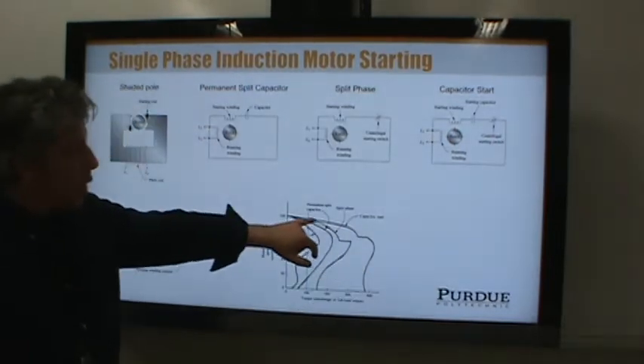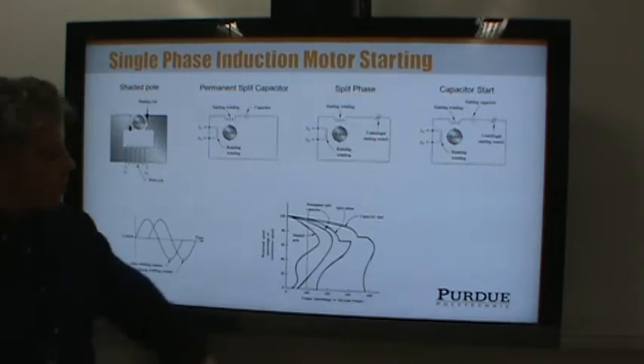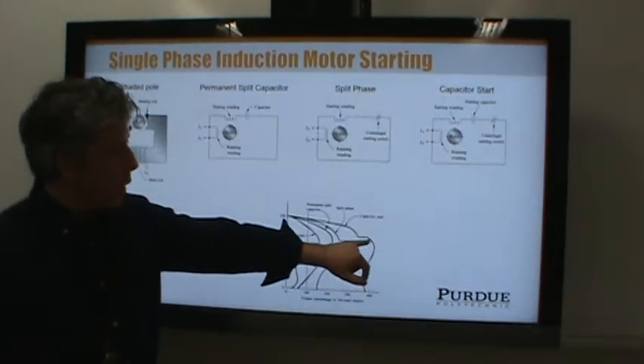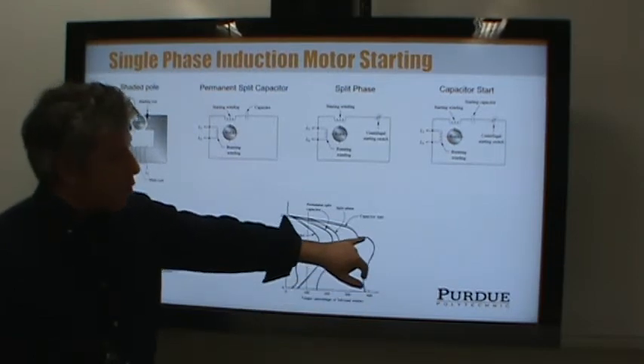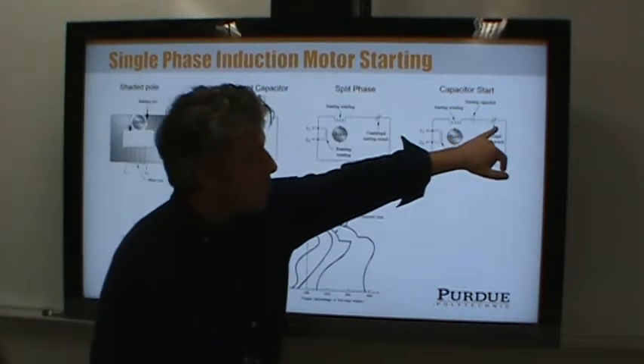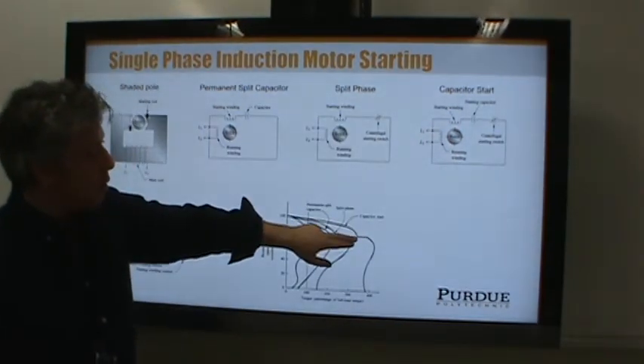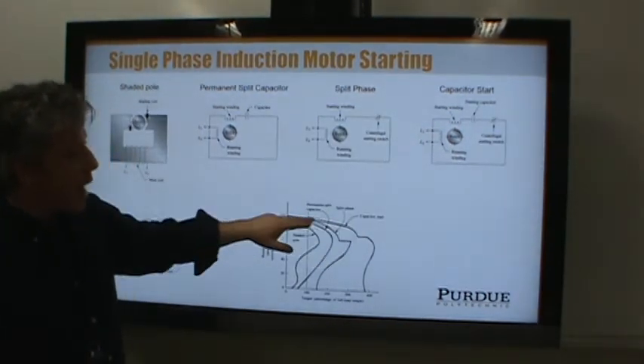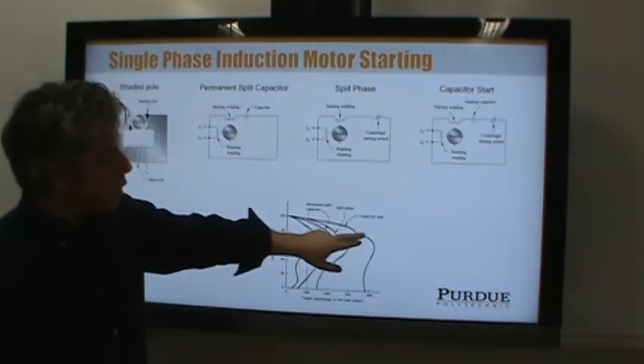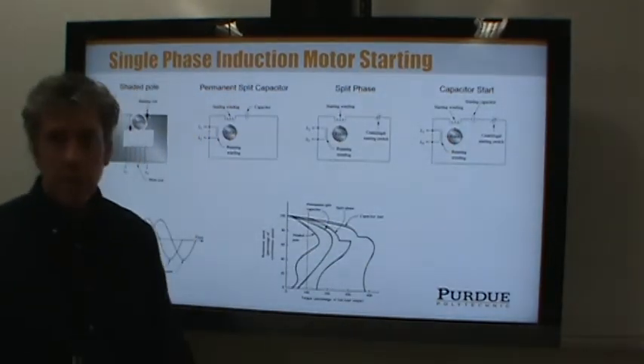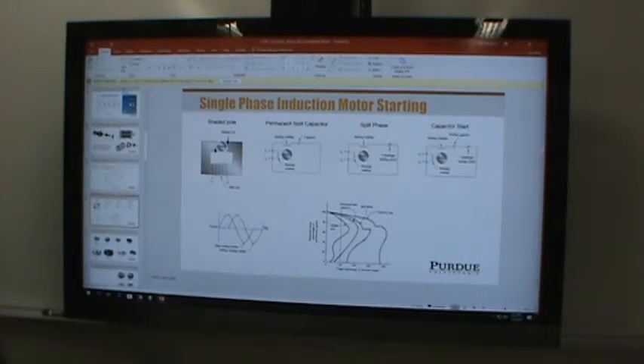This motor generates a lot of torque and power for its size. Initially there's more power but less efficiency, and then right at that transition point the centrifugal switch clicks and the start winding is taken out — you generate a little less torque but at higher efficiency. In the upper region you're using the running winding; in the lower startup region both windings are active.